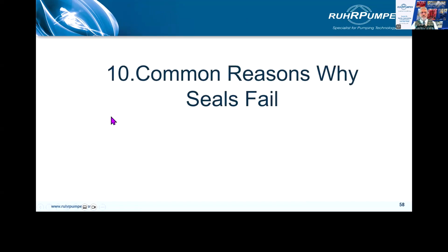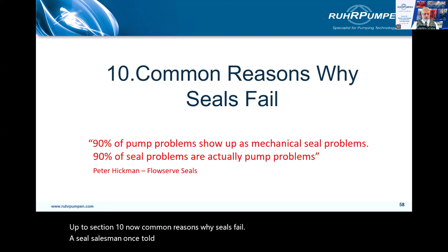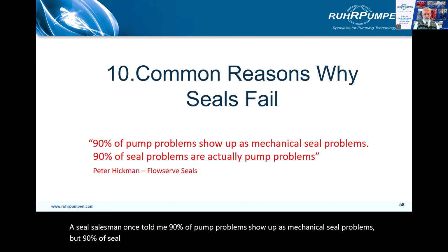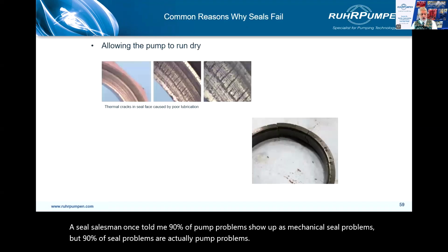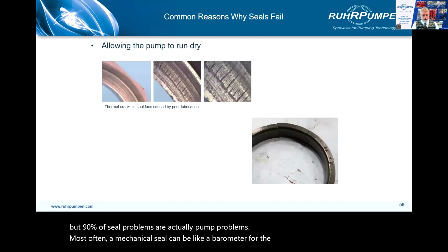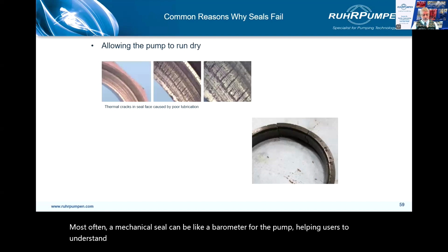Up to section 10 now, common reasons why seals fail. A seal salesman once told me 90% of pump problems show up as mechanical seal problems, but 90% of seal problems are actually pump problems. Most often, a mechanical seal can be like a barometer for the pump, helping users to understand the state of health of the pump. At other times, failure is as a result of poor seal selection or seal installation errors.